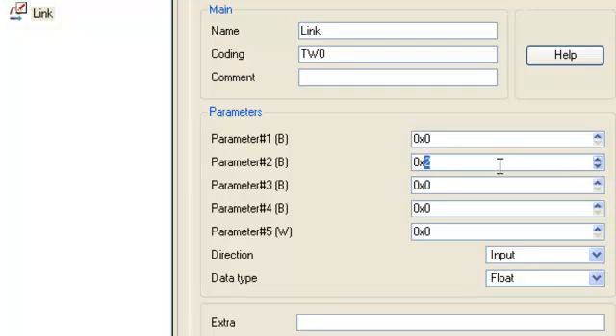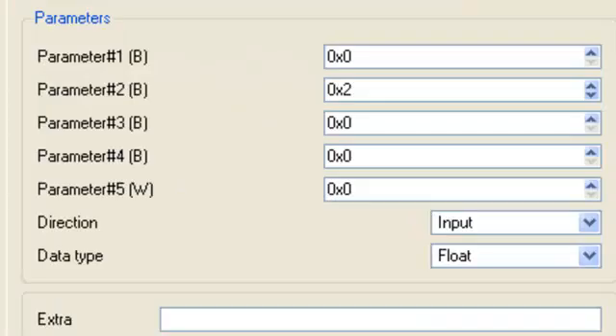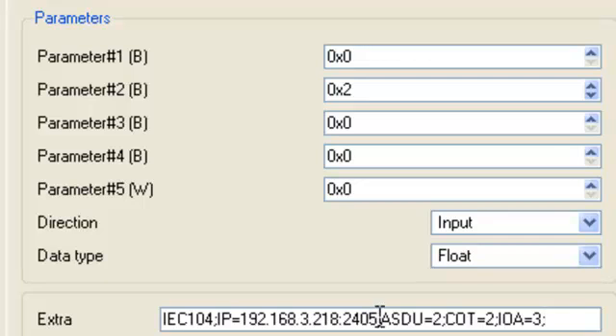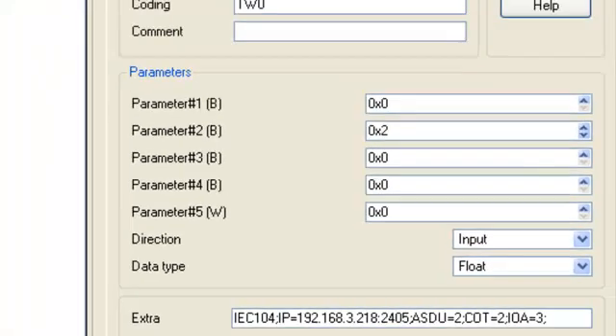And change the only variable, parameter number 2, address of PLC/server. In our case it equals 192.168.3.218:2405. In the field Extra, let's type the next string: protocol type, IP address of PLC, using port, protocol parameters. Now let's create four components for reading/writing PLC signals using the bind and play technology.